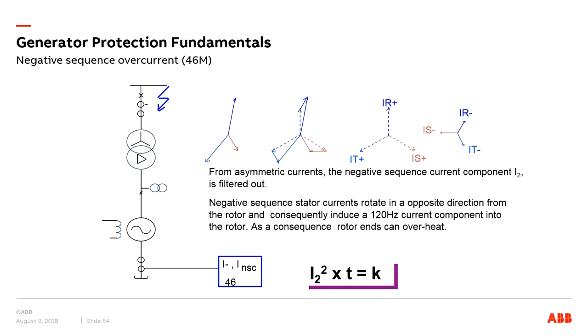Then there is a negative sequence overcurrent protection. Negative sequence current is caused by unbalanced loads. It could be due to non-transposed transmission circuits, unbalanced system faults, series faults, circuit breaker pole discrepancy, or open circuits. The negative sequence current flows through the stator winding, inducing negative sequence voltage in the rotor winding. This can result in a high rotor current that damages the rotor winding. The frequency of this induced current is approximately twice the supply frequency, and due to skin effect, it encounters high rotor resistance, which leads to excessive heating, even with phase currents less than the rated current of the generator.